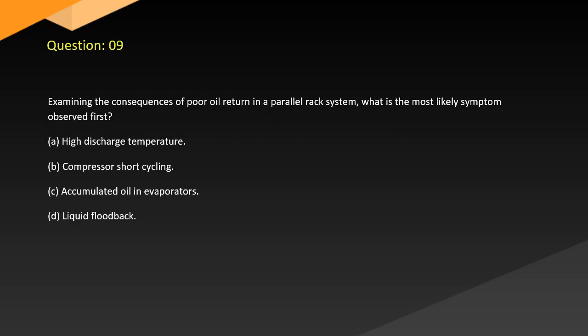Question 9. Examining the consequences of poor oil return in a parallel rack system, what is the most likely symptom observed first? A. High discharge temperature. B. Compressor short cycling. C. Accumulated oil in evaporators. D. Liquid floodback.